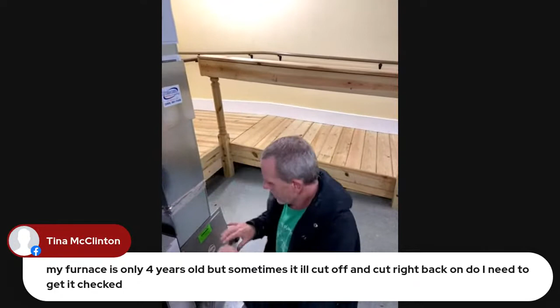Especially with the newer furnaces, there are so many safeties built in that it's really difficult to have a furnace fail in a way where it's going to blow something up or something along that line. There are a lot of sensors, and sometimes something will just get too hot or whatever. But if it's shutting down continuously and you're having to restart it, that's usually saying there's a problem.